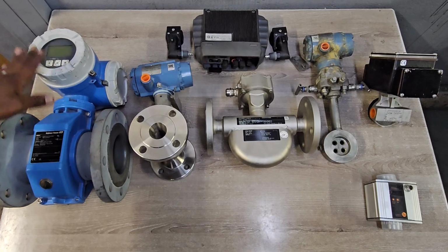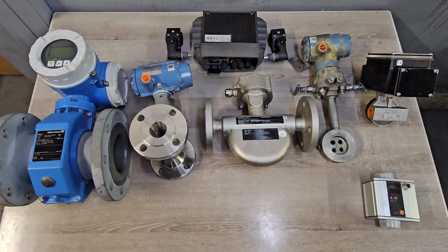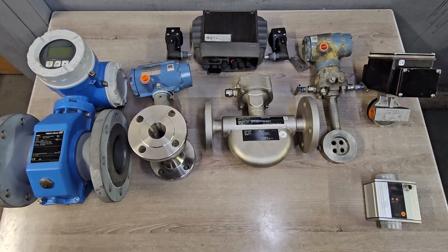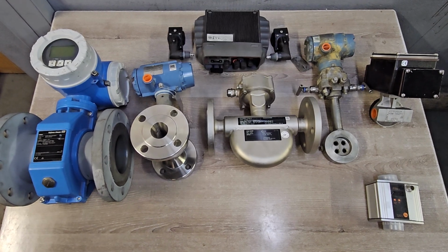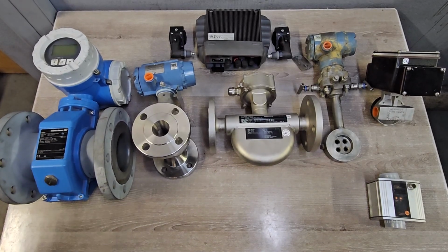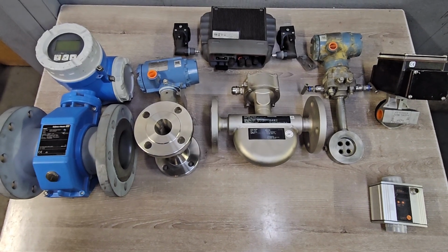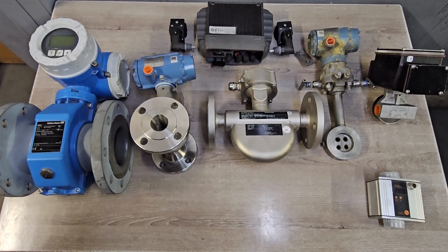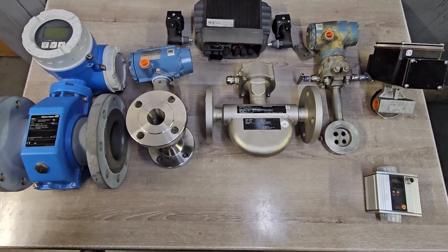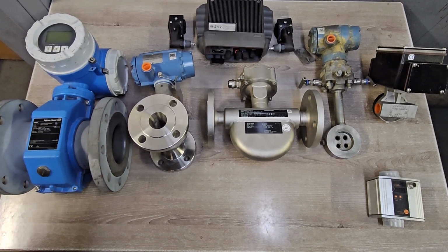On the left, this side, this one is a mag flow. It is based on the principle of an electromagnetic field. It's usually used for liquids that are conductive because there is a magnetic field involved. So you get poles or electrodes. Let me put it this way: you get electrodes more like in your magnet, whereby you've got a north pole and the south pole. So there's a magnetic field traveling from the north to the south, or from one electrode to another electrode. And then when your liquid starts flowing in that flow meter, it will distort that magnetic field.